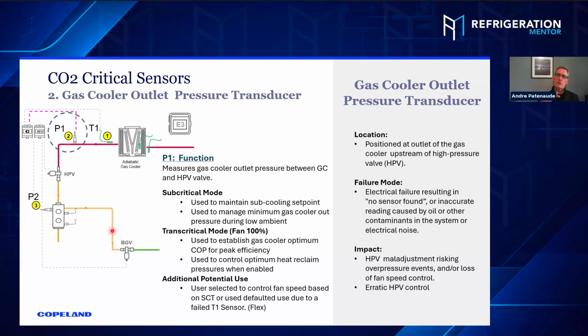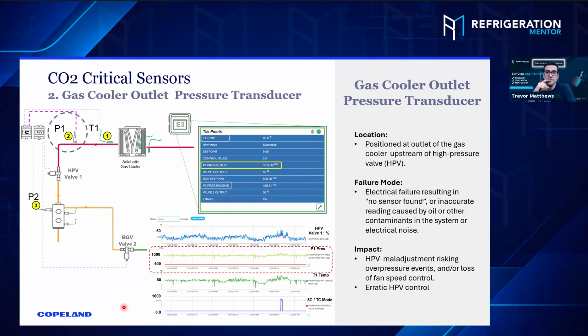Well, you're right, because on our condensing unit control, we've taken the PIDs out. Yeah. They're gone. It's different AI algorithms that we've used in order to smooth that out. But you're absolutely right. If you can smooth out your fan modulation, that means the T1 temperature is more constant. If that T1 temperature is more constant, that means you control subcooling more accurately. That means the flow through the high pressure valve is steady. That means your flash tank is smooth. That means your bypass mass flow is smooth. That means your compressor cycling is smooth. They're all interconnected. Yeah. Absolutely.